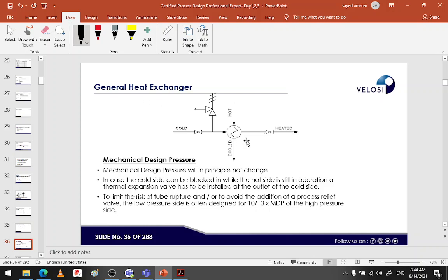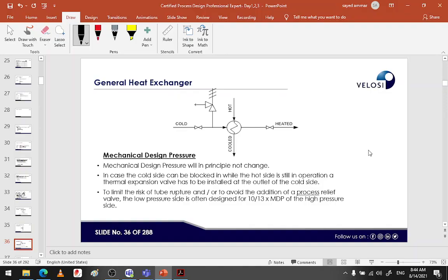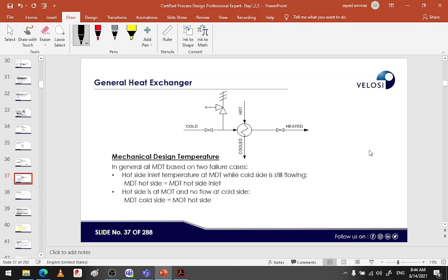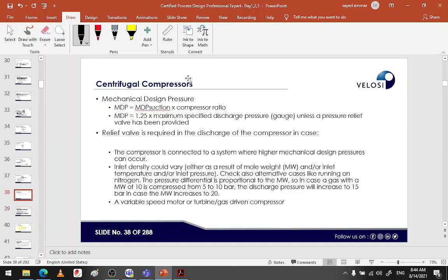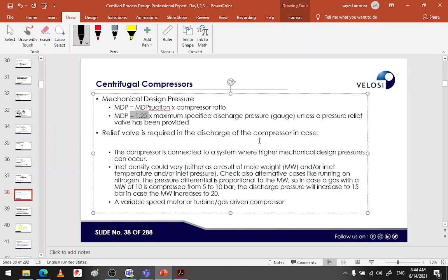This is the typical arrangement for a heat exchanger. I'm not interested in it now. I will show you a complete handbook for this typical arrangement, which will help you during your drafting. Centrifugal compressor, like centrifugal pumps, I will go for 1.25 of the maximum operating pressure of the compressors. I will go for the 1.25 to make sure that I am on the safe side. There's a lot of specs. Some like Shell will go 1.15, BP will go 1.2, and ExxonMobil will go for the 1.25.